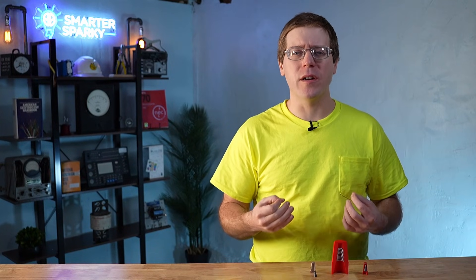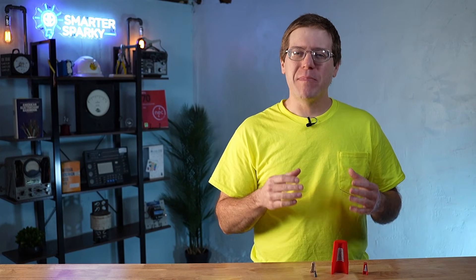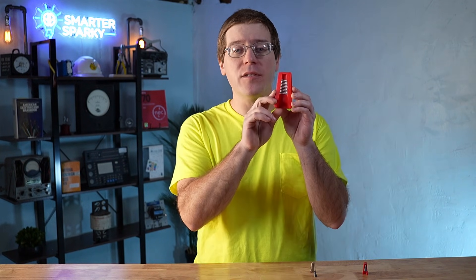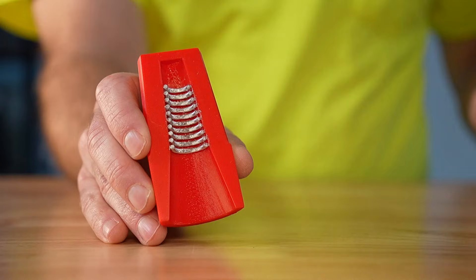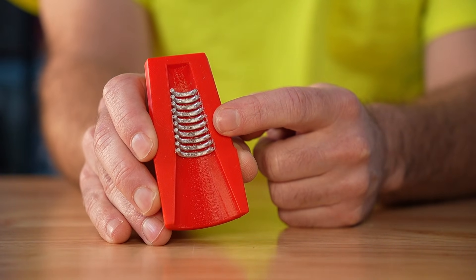Before we talk about how to use a wire nut correctly, we need to understand what it's actually doing. Most people think of a wire nut as just a plastic cap. While that's partially true, there's a little more going on under the hood. Here's a simple cutaway of a wire nut. Notice there's a metal spring insert within the wire nut. That's what's actually holding the wires together.